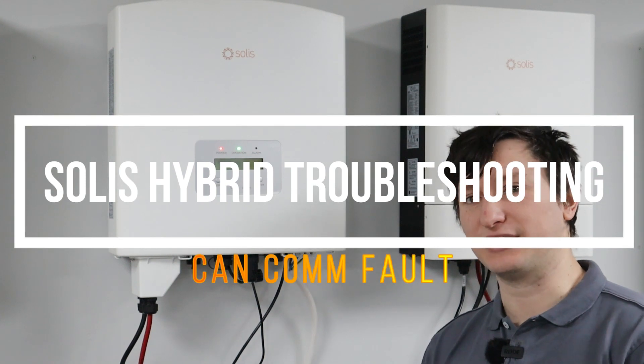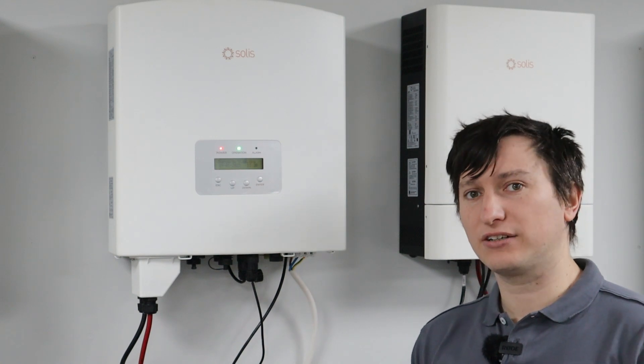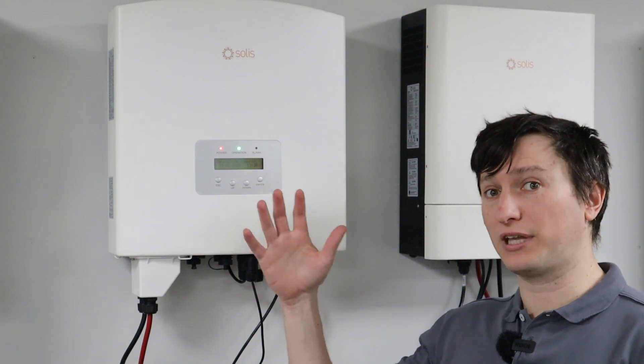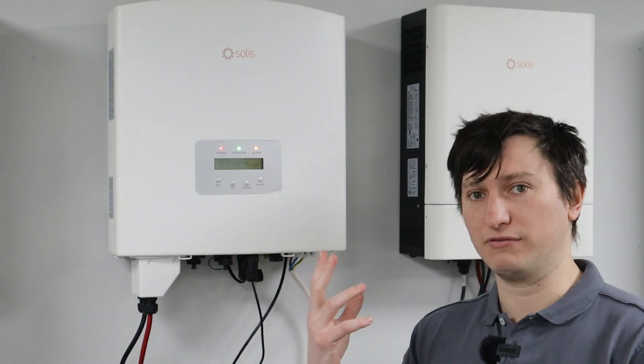Hi, good day. This is Paul from Solis. Today I'm going to talk about some troubleshooting methods for CAN COMM faults. CAN COMM faults is a fault code that appears on the inverter when it's not detecting CAN communications between the battery and the inverter.